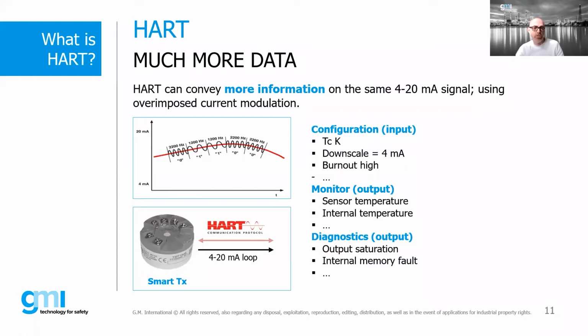Communication starts from the master to the slave. There can be up to two masters connected on each HART loop, while the slaves are typically field devices such as sensors, actuators, and controllers that answer questions. The applications that exploit this technology allow remote interrogation of process variables, cyclical access to data, calibration, access to operating parameters, and instrument diagnosis. Devices with HART communication superimpose an electrical signal on the analog signal, with which they can be monitored and programmed depending on the manufacturer and the interface system. The HART protocol, also defined as open, does not allow complete communication of all available parameters with any instrument, but requires the presence of the drivers for the device in question.